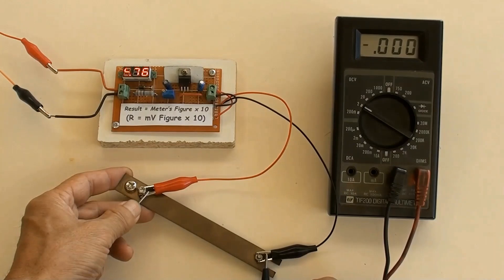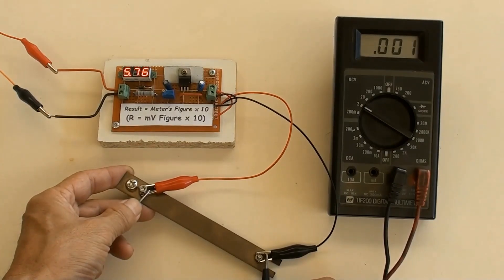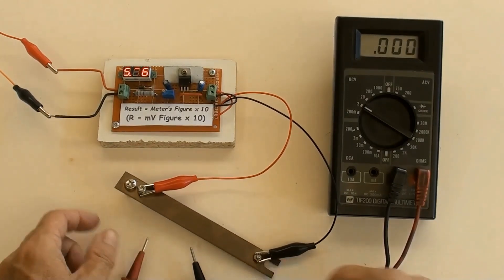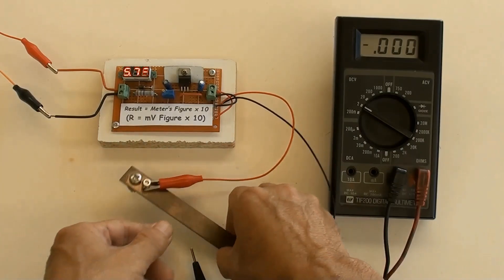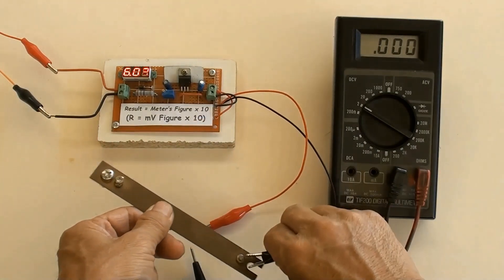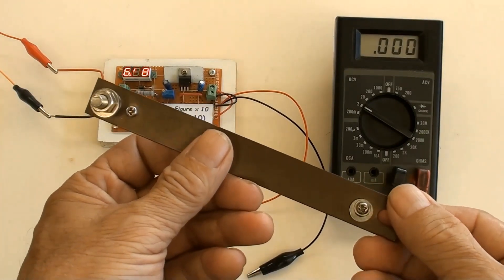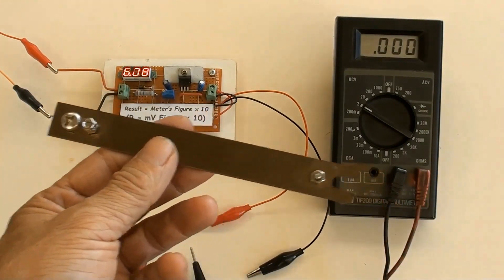Measuring this shunt. Multimeter indicated 0.001 volt or 1 millivolt, then using formula on the sticker, 10 times equals 0.01 ohm, in other words, 10 milliohms. So this shunt is 10 milliohms.